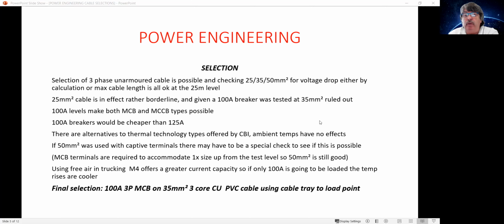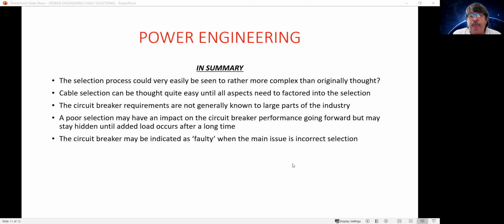So the point of today was to look at all of these options, but with a view from the circuit breaker manufacturer's side as an added complication. As I said, you see nothing of this in any of the wiring codes per se, but this is to bring the knowledge out there, because one day you might be called to a site where this type of arrangement effectively looks like it fits the wiring code, but the breaker, and I'm not saying it's a faulty breaker, the breaker and the technique of a thermal breaker may have an effect on what's happening on that site. So I hope you got something out of today's discussion. It does sound a heck of a lot more complex than originally thought, I'm sure.